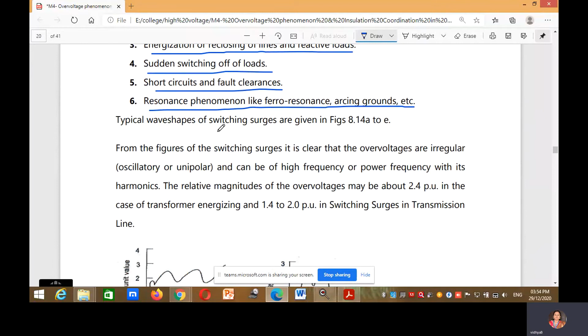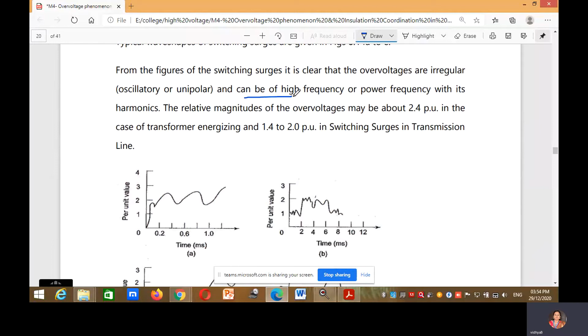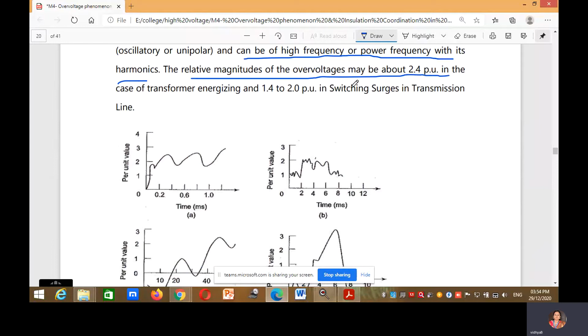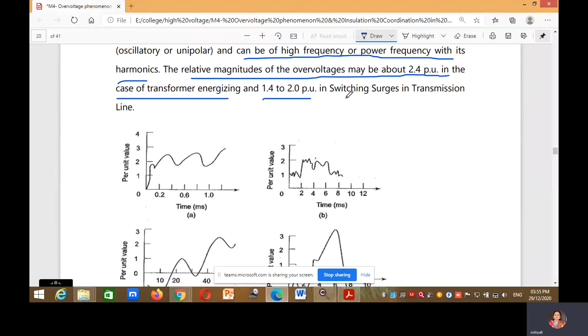Typical wave shapes of switching surges. From the figure of the switching surges, it is clear that overvoltages are irregular; they may be oscillatory or unipolar. They can be of high frequency or power frequency with its harmonics. You can observe the figure. The relative magnitude of the overvoltage may be about 2.4 per unit in the case of transformer energizing and 1.4 to 2.0 per unit in switching surges in transmission line. This is the graph for that.